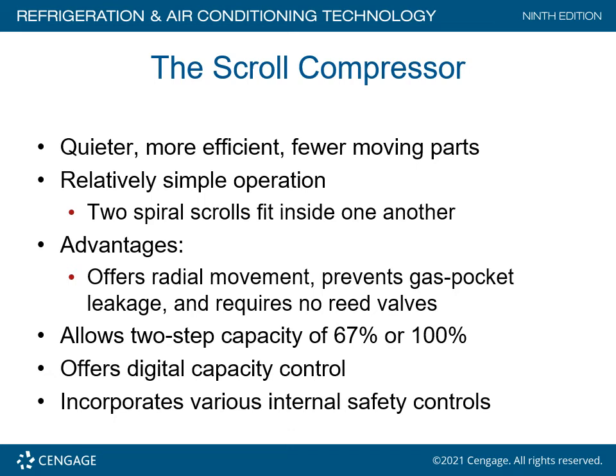Scroll compressors are quieter, more efficient, and have fewer moving parts. Probably 90% of the air conditioning equipment you'll work on in the field uses scroll compressor design. Two spirals (scrolls) fit inside each other. Advantages include radial movement, which prevents gas pocket leakage and requires no reed valves. They allow two-step capacity of 67% or 100% pumping, offer digital capacity control, and incorporate various internal safety controls. Essentially, you can ramp up and ramp down the speed of a scroll compressor.